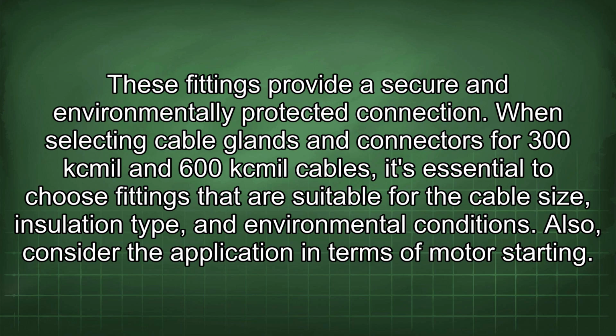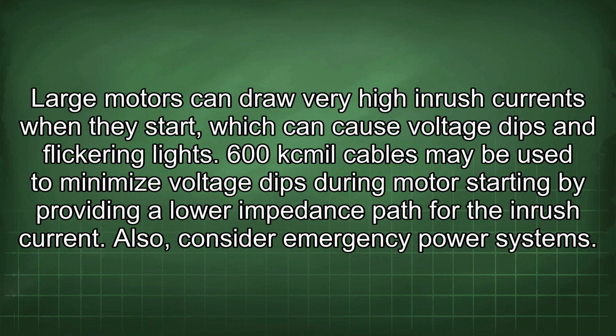Also, consider the application in terms of motor starting. Large motors can draw very high inrush currents when they start, which can cause voltage dips and flickering lights. 600kcmil cables may be used to minimize voltage dips during motor starting by providing a lower impedance path for the inrush current. Also, consider emergency power systems.